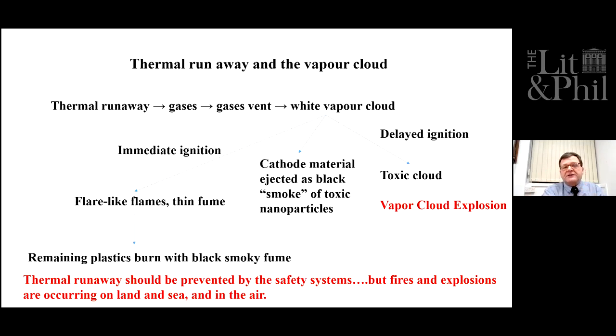So the sequence of events is as shown here. Thermal runaway produces heat and gases, and the gases vent. Commonly what happens is that small particles of the cathode, the heavy metal oxides, are vented first as a black cloud that looks like black smoke. Then you get the vapor cloud.